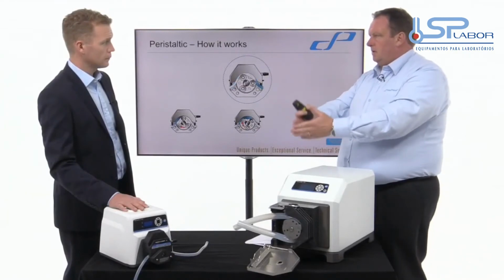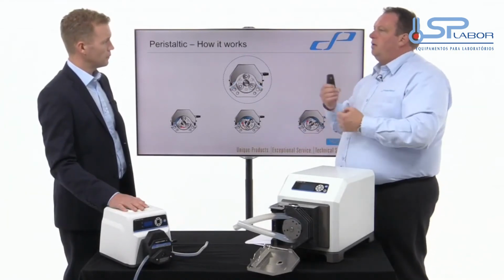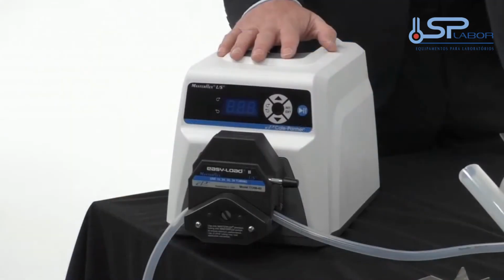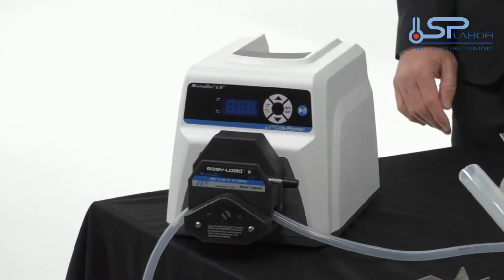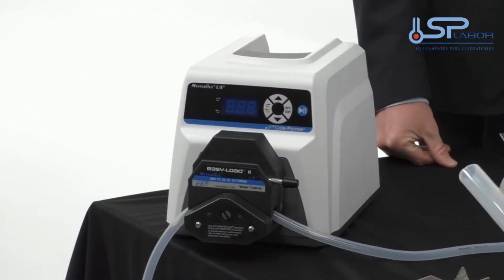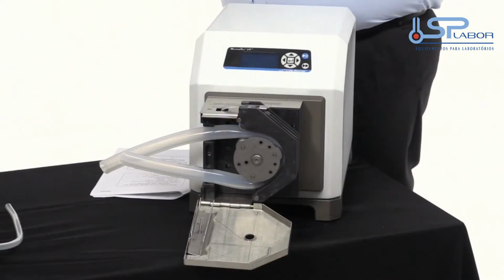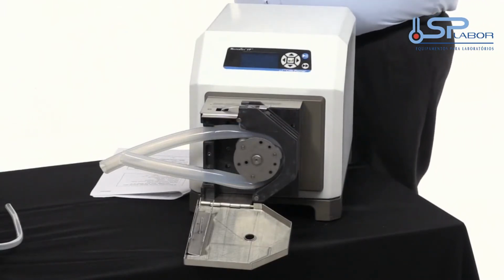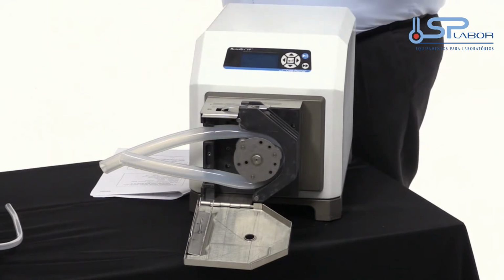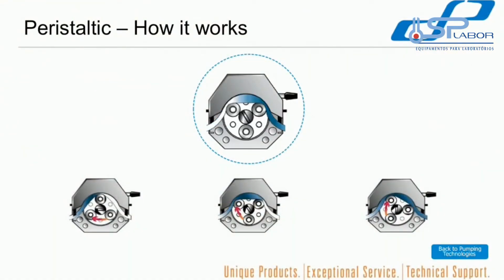And because your process is contained within the tube, you're not breaking process. So again, from a hygienic point of view, you're not letting ingress of the outside to the inside, or the inside to go outside. You're maintaining hygienic sterility. And you can use them as what we call a single-use system, where you just take it and throw it away, then put a new tube in, and you're clean again, because you can have many different tubes irradiated, many variations. It is a wonderful pump.